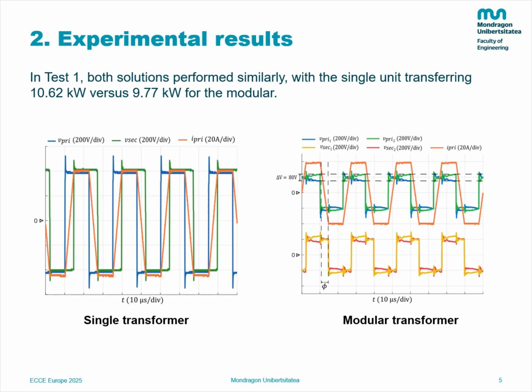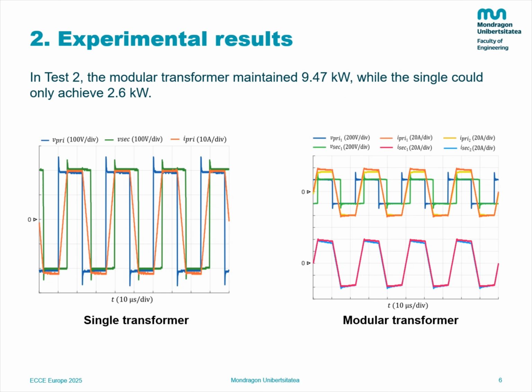This discrepancy between the difference in magnetizing inductance and unequal voltage distribution may be due to the handling of the cores during manufacturing. Such manipulation can alter the values, leading to discrepancies in the measured voltage. In test point 2, the modular transformer maintains 9.47 kilowatts, while the single transformer could only achieve 2.6 kilowatts. Therefore, the power achieved by the modular transformer is 3.6 times higher than the single transformer.